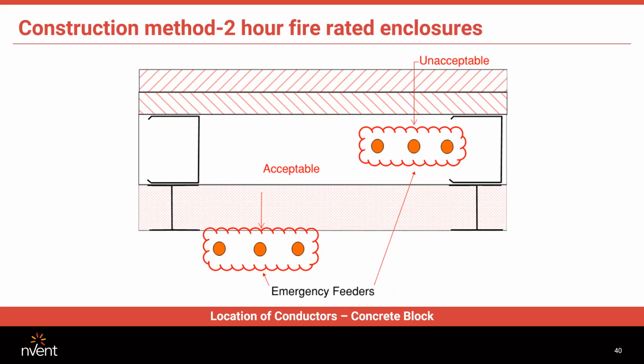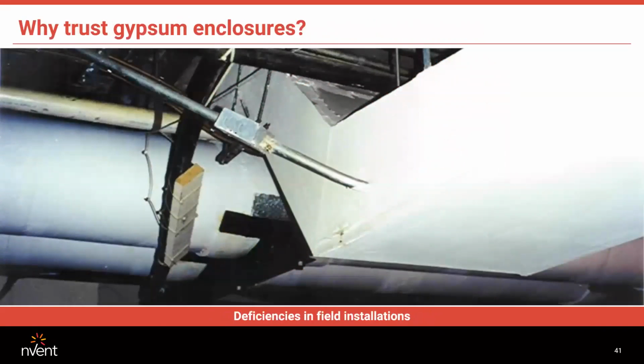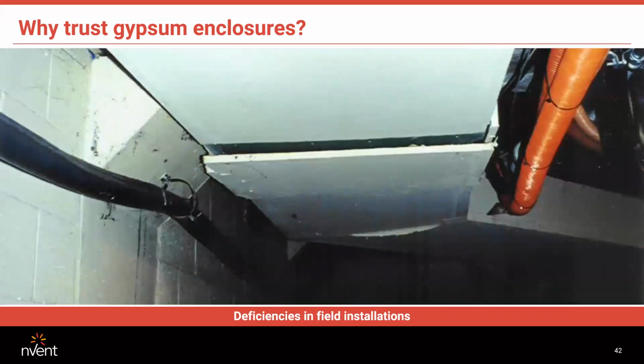So you can see, if you've got a vertical shaft going up a brand new building, yeah, you can do this. But if you have a horizontal run or a run in an existing building, this is going to be very difficult to do, because it takes up a lot of space. It's trade sensitive. And then over time, issues arise. You can see by this slide, someone needed to run some conduit. The enclosure was in its way, so the guy just poked a hole through the enclosure with this conduit, compromising the system. Also, over time, they deteriorate and begin to fall apart. Because this is falling apart, this would offer absolutely no protection at all in the event of a fire. The fire would go right through that.